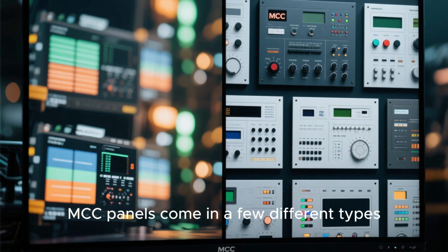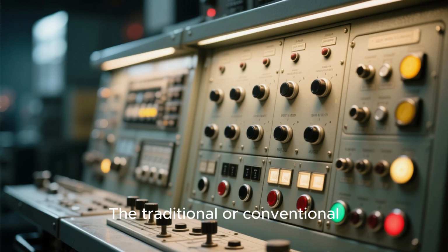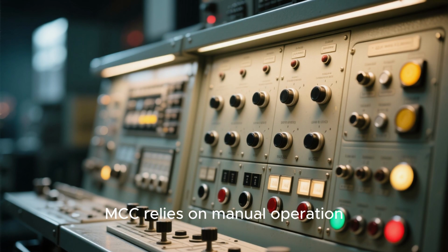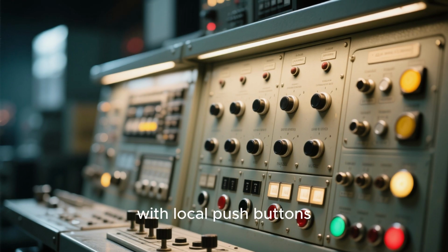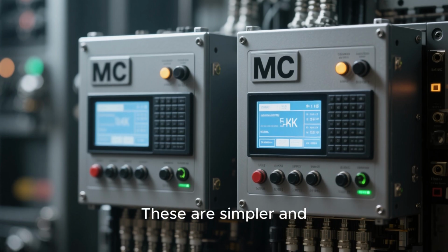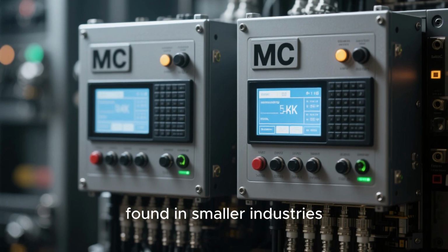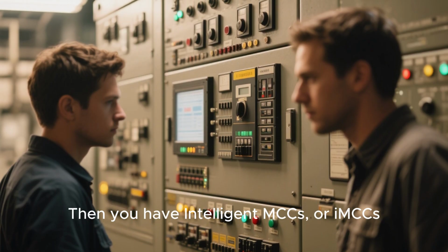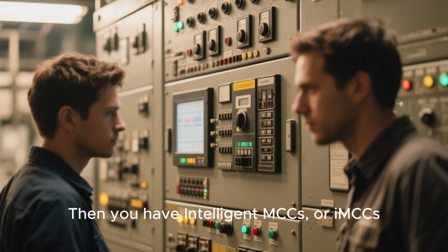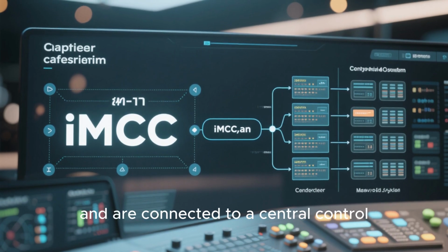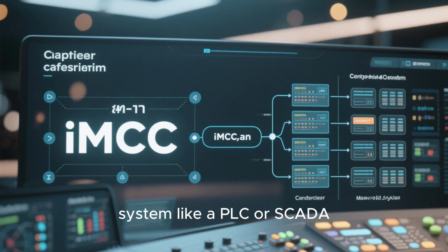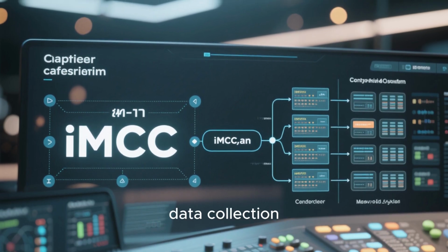MCC panels come in a few different types. The traditional or conventional MCC relies on manual operation with local push buttons. These are simpler and found in smaller industries. Then you have intelligent MCCs or IMCCs. These are the smart ones. They use digital relays and are connected to a central control system like a PLC or SCADA, allowing for remote monitoring, data collection, and advanced diagnostics.